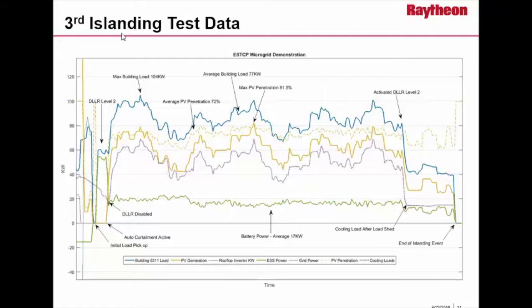Another interesting thing we added to this project was the ability to curtail the HVAC loads. Some of these big load steps are when we did a level 2 load curtailment, essentially just running the fans, not the compressors. You can see these big drops in power here. The cooling load is a big contributor, and when it was reduced, we were able to reduce the effective load of the building on demand.